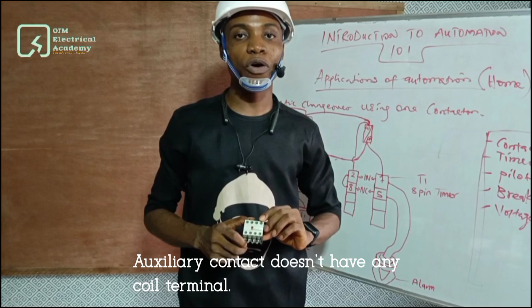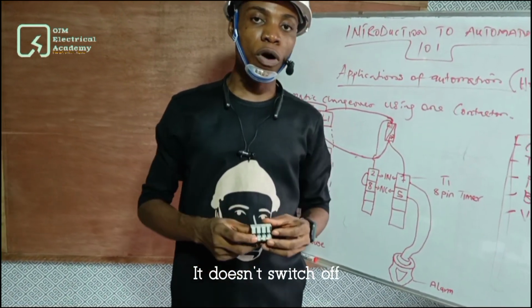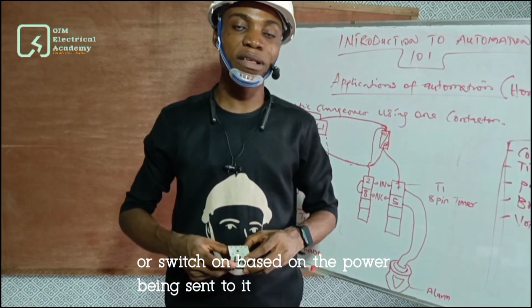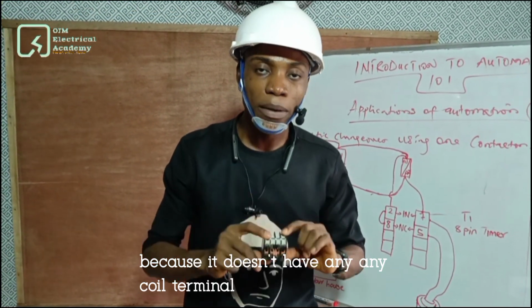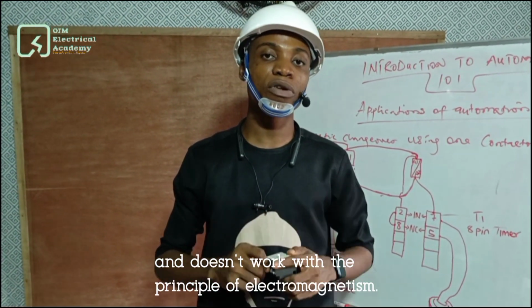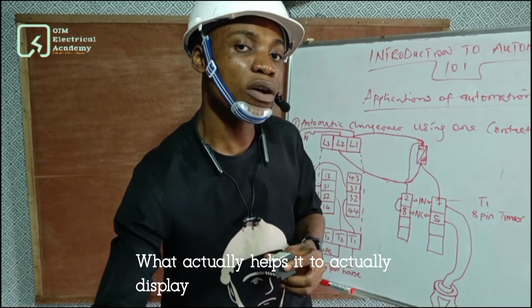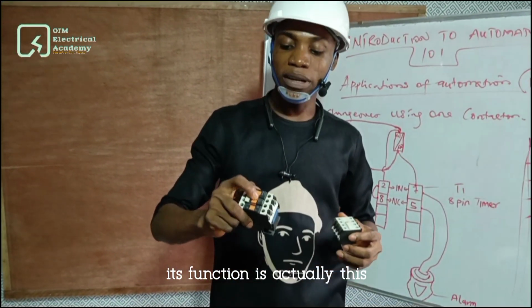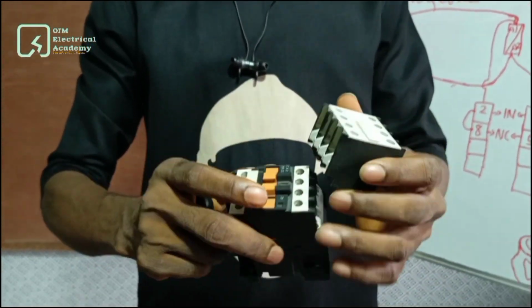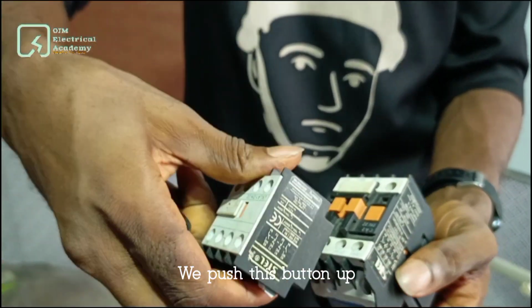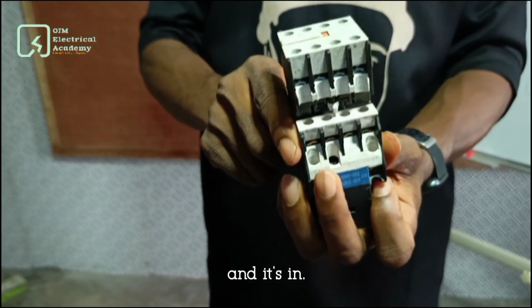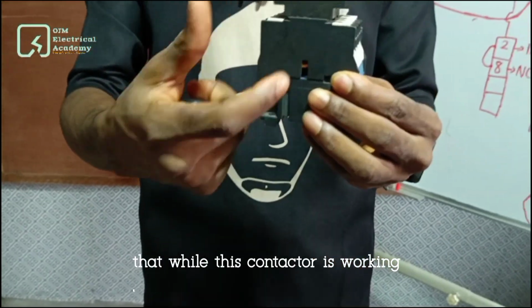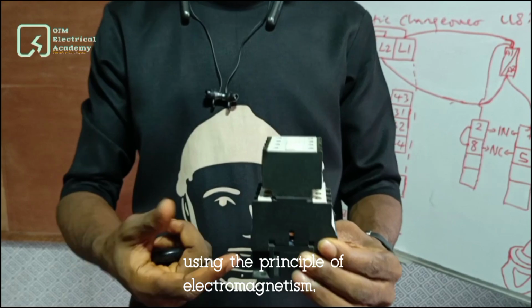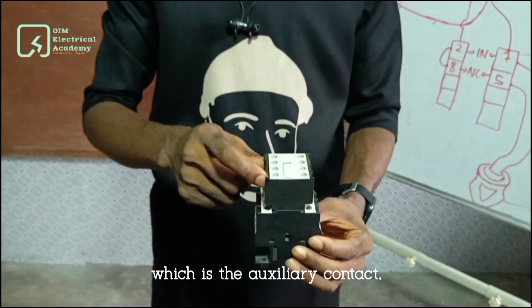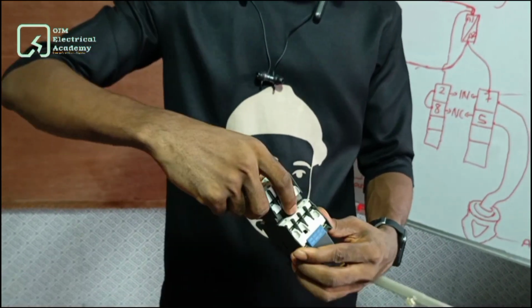The auxiliary contact doesn't have a coil terminal, so it doesn't switch on or off based on power sent to it, since it doesn't work on the principle of electromagnetism. What activates it is this part on top of the contactor. This is how to place it in: we push this button up and connect it this way, and it's in. So while the contactor works using electromagnetism, the auxiliary contact works alongside it.